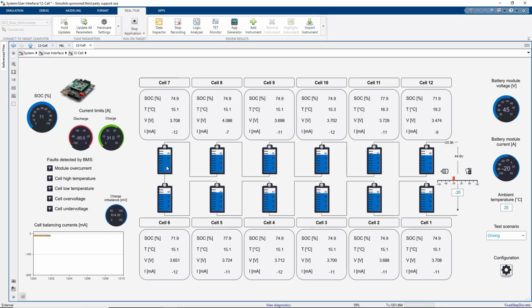Let's discharge the battery with 20 ampere. The BMS allows a discharge limit of minus 90 ampere for the present battery state. So if we override this value by minus 120 ampere, the BMS immediately triggers an overcurrent fault.